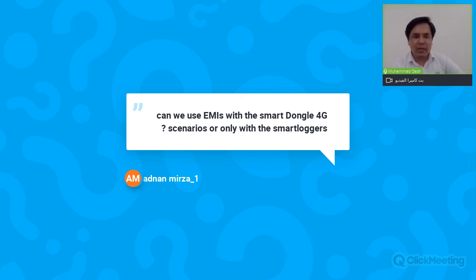Adnan Mirza is asking, can we use EMIs with the smart dongle 4G scenario or only the smart logger? Good question. EMIs, if most of you are not aware, are actually environmental monitoring instruments, normally known as weather stations. These sensors cannot be used with the 4G dongle because it doesn't have connection points for the COM port or the Modbus TCP connection. So the only way that you can use a weather station is when you have a smart logger which can also speak with your sensors.